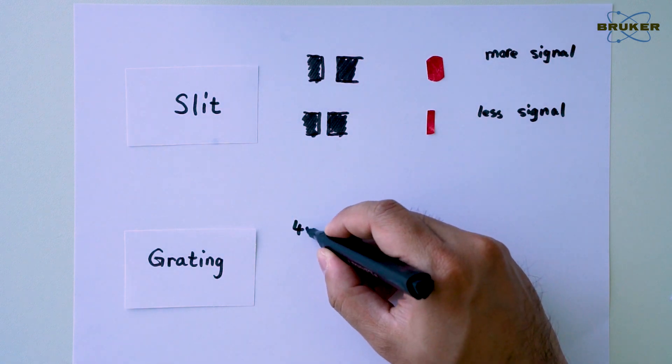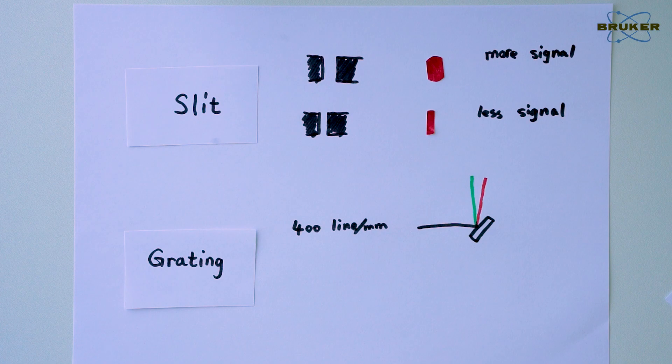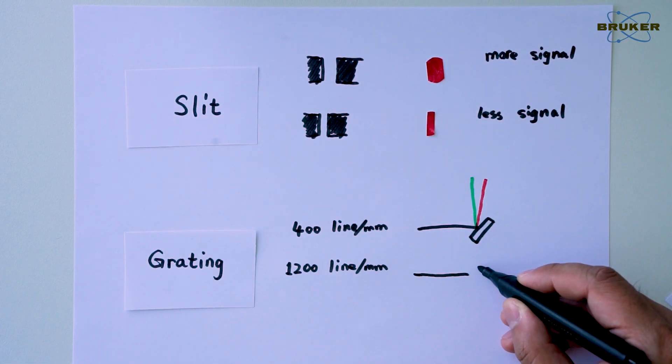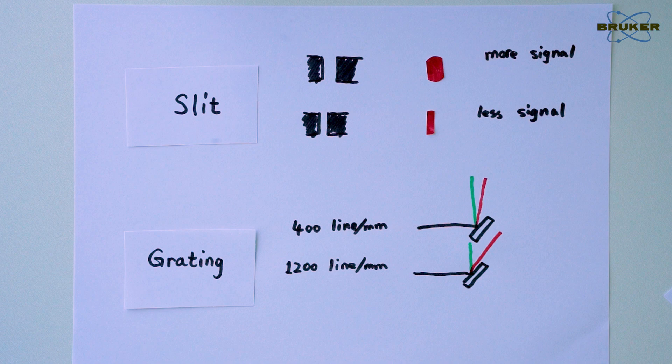We can also change the grating and increase the so-called line density. This spreads the Raman signal over a wider angular range, improving the spectral resolution. But again, less light will reach the individual CCD pixels, and we lose sensitivity.